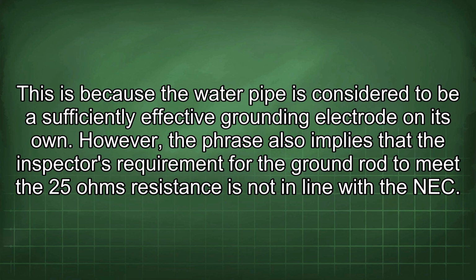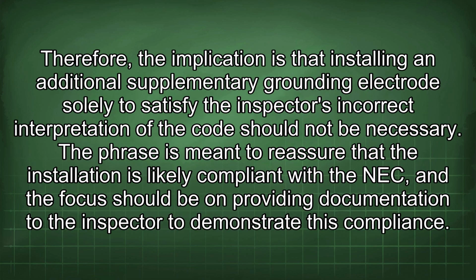This is because the water pipe is considered to be a sufficiently effective grounding electrode on its own. However, the phrase also implies that the inspector's requirement for the ground rod to meet the 25 ohms resistance is not in line with the NEC. Therefore, the implication is that installing an additional supplementary grounding electrode solely to satisfy the inspector's incorrect interpretation of the code should not be necessary. The phrase is meant to reassure that the installation is likely compliant with the NEC, and the focus should be on providing documentation to the inspector to demonstrate this compliance.